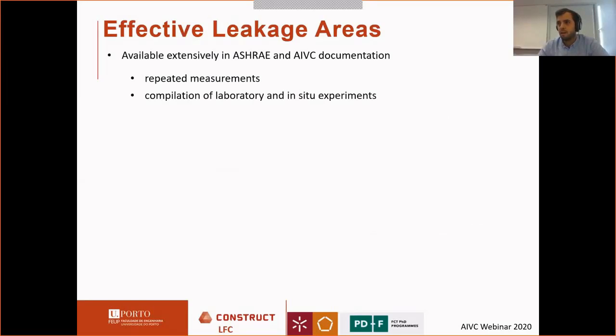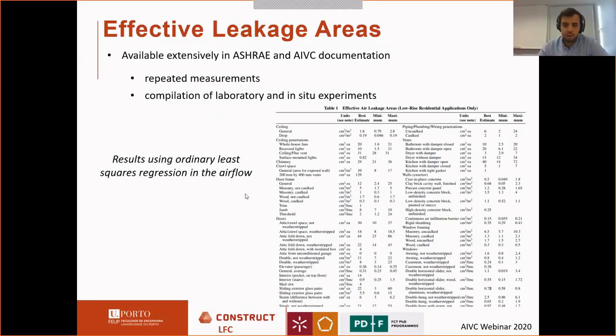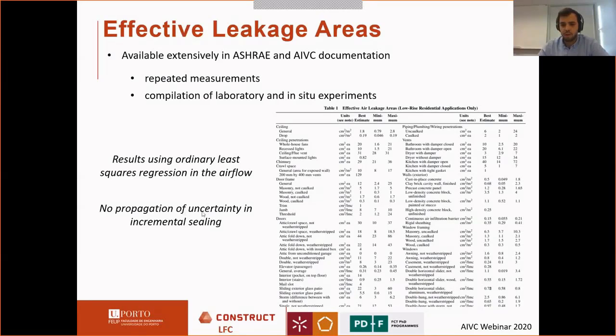Effective leakage areas are extensively available in ASHRAE and IEA documentation. They are the result of repeated measurements and compilation of laboratory or in-situ experiments. But when they are derived in a reductive sealing way, normally only ordinary least squares regression is used for the airflow — they don't take into account the variance in the pressure difference, nor the propagation of uncertainty through these incremental steps.